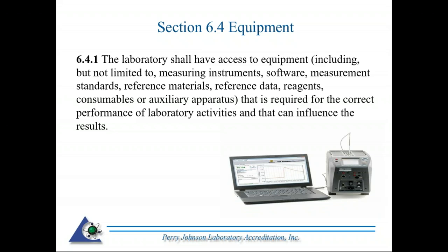6.4.1, the laboratory shall have access to equipment, including but not limited to measuring equipment, software, measurement standards, reference materials, reference data, reagents, consumables, or auxiliary apparatus that is required for the correct performance of laboratory activities and that can influence the results. So like I said, you have to have the tools to do the job. You have to have equipment that is capable of meeting your accuracy requirements, and not just hard equipment that we have depicted here, such as a temperature bath there. Also things such as software and other things that are referenced here.